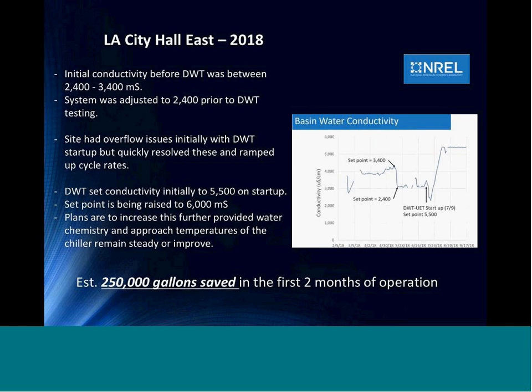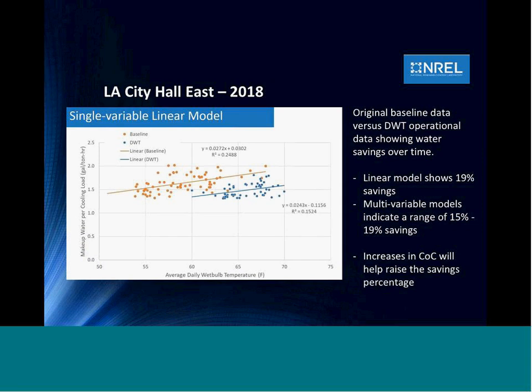It was quite interesting. Since we've started our process, we had an initial set point of 5,500. Actually, we've just raised it to 6,000. We usually push anywhere from 7 to 8,500 microsiemens conductivity. And this, again, was without any kind of additions of acids, corrosion inhibitors, or scale inhibitors. The first 2 months, we actually showed a net savings of about 250,000 gallons in the process. Next slide, please.